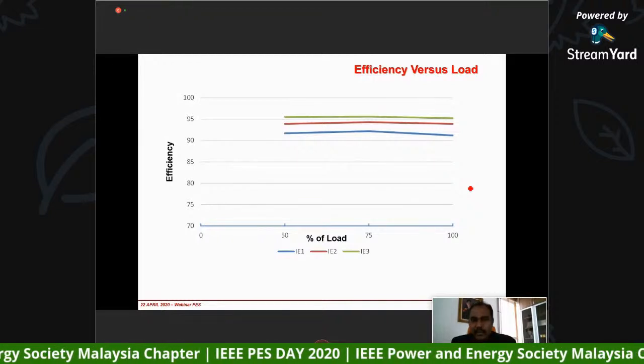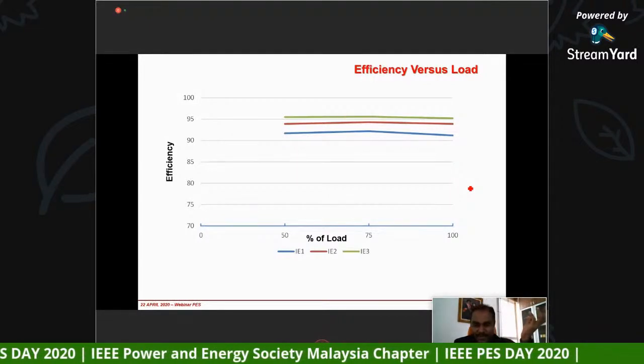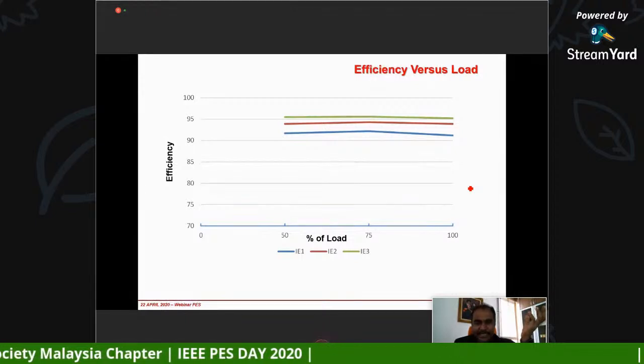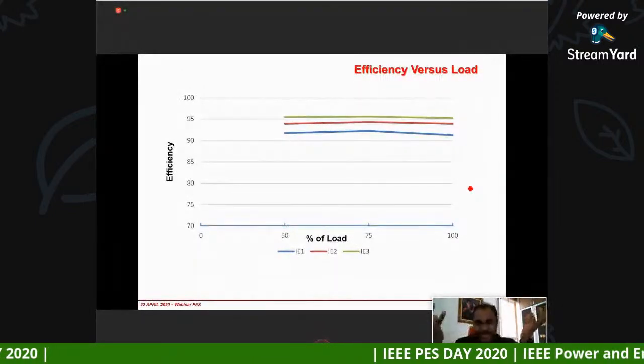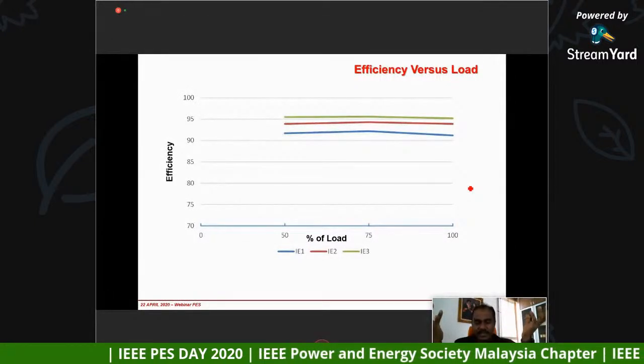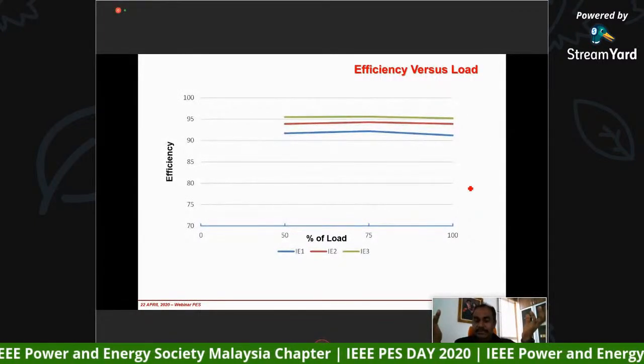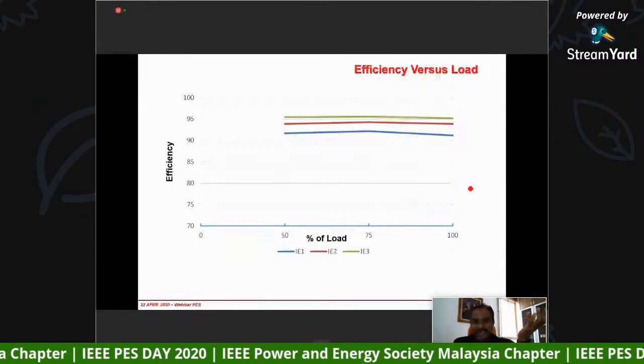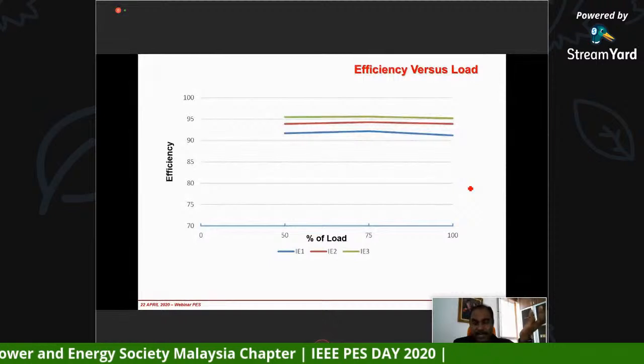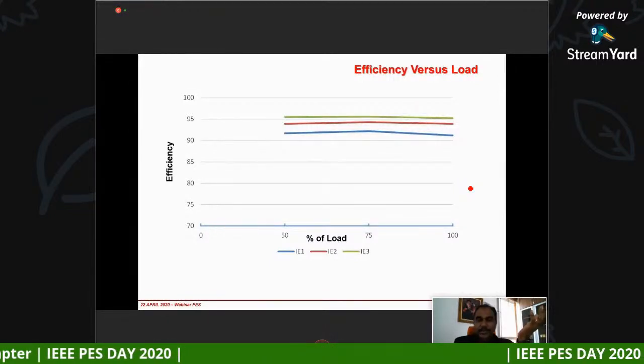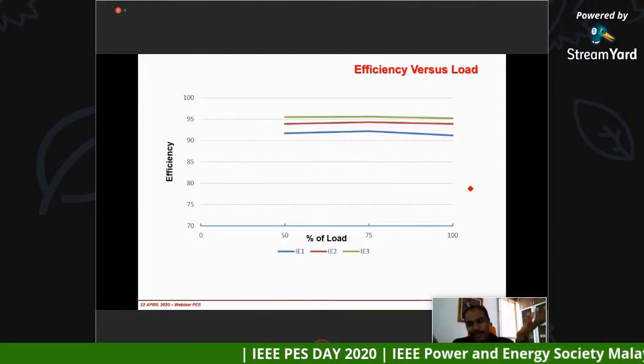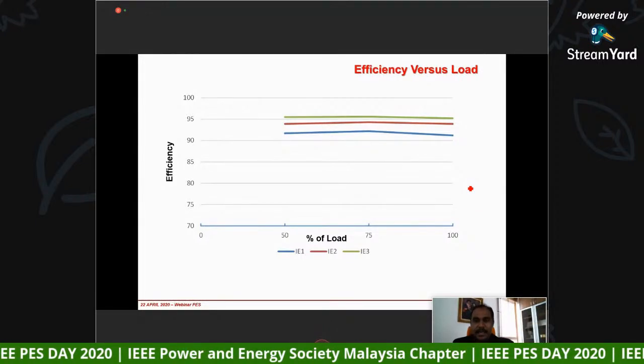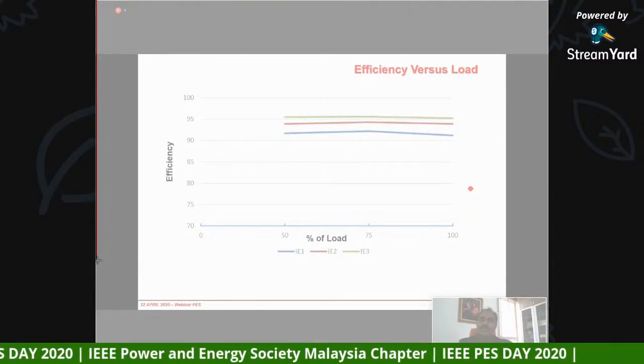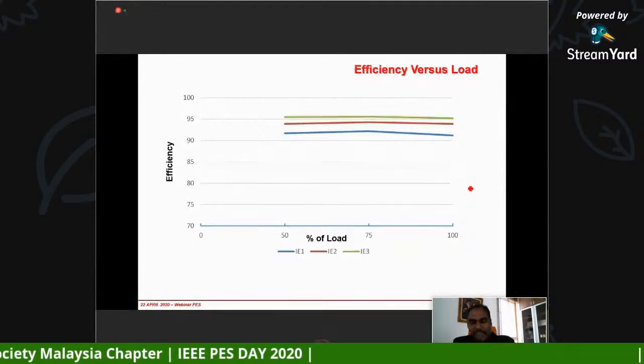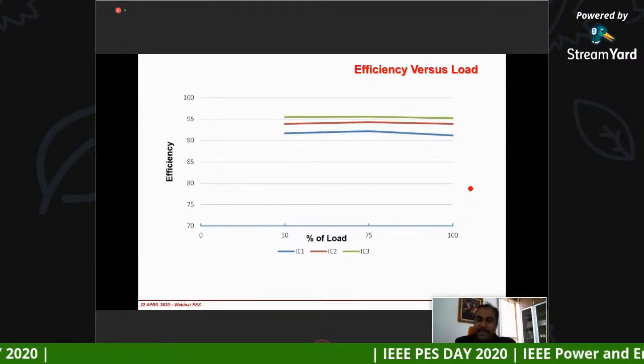for example, now you're using a 40-watt fluorescent light. Then I say, now I'm going to change this fluorescent light to an LED light, which is going to give the same lux while only consuming 5 watt. Yes, that is straightforward, because more or less the light will consume about the same power all the time when it is turned on. So obviously you can compare 40 watt to 5 watt. Obviously, your 5 watt is going to give you a lot of savings. But when it comes to the motor, remember, when you have a 30 kilowatt motor, for instance, it is not going to develop mechanical power of 30 kilowatt all the time. It depends on the load.